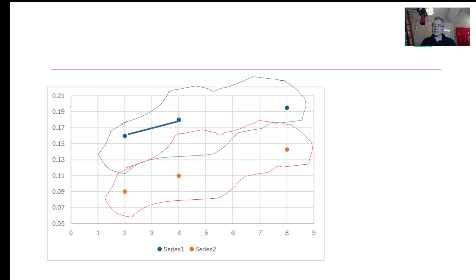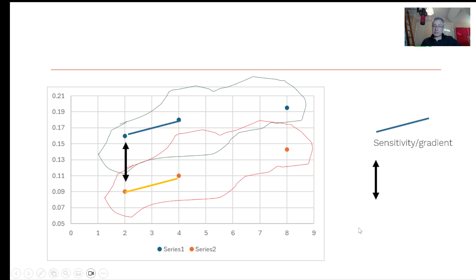So I put them side by side here. You kind of get a similar trend in both solutions. This is the ZP test solution, and this is that third-party test solution. You get a similar trend in both solutions. You know that the signal changes proportionally to concentration, but it's actually the offset between the two that's giving you a concern. I'll mention in a minute that if you were testing the same concentration of potassium in urine versus sweat versus saliva versus blood as an extreme, you would get a different offset every time. So these sensors are sensitive, or at least the offset is sensitive to the solution that you're actually using. I'll dig into that a little bit deeper.